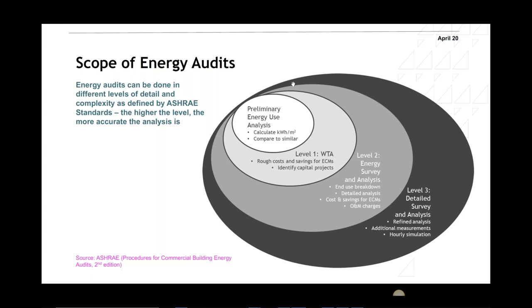So there's the preliminary energy use analysis. That's mainly to calculate your EUI, or energy use intensity, or energy utilization index. We call it EUIs. That's basically looking at the whole energy consumption for a year, dividing that by the square meter, normally the air conditioned area or the GFA, and that would be the EUI. So we're normalizing the energy consumption. Then you would compare it to similar buildings.